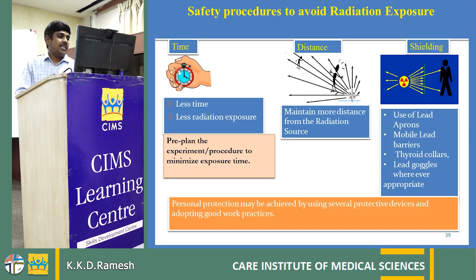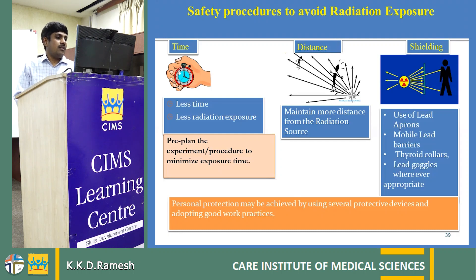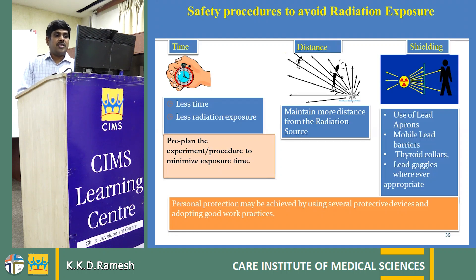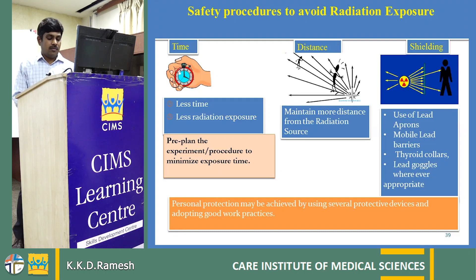Safety procedures to avoid radiation exposure include Time, Distance, and Shielding. Less time means less radiation exposure — pre-plan your procedure to minimize exposure time. Try to maintain as much distance as possible, and shielding sufficiently reduces radiation exposure to both staff and patients.